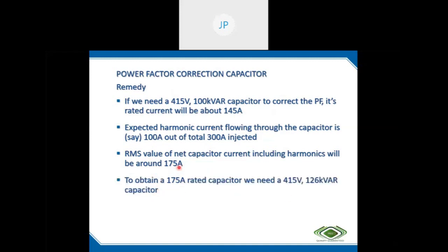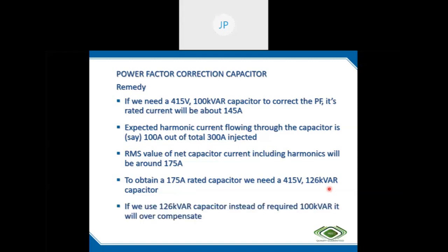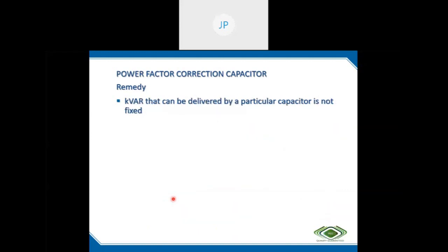To obtain 175 amps, we need a 126 kVAr capacitor. If we use a 126 kVAr capacitor, what will be the effect? Instead of 100, we are using 126, so it will overcompensate, or the voltage may damage equipment, again another issue. So what can we do? The delivered kVAr rating of the capacitor is not fixed. You may be confused by that, so I will explain it.